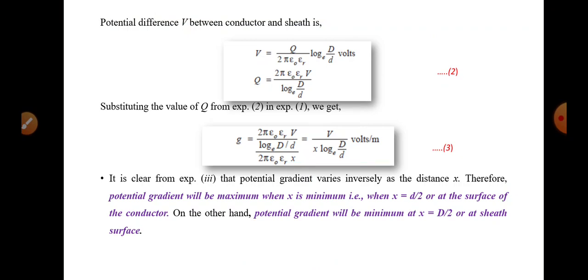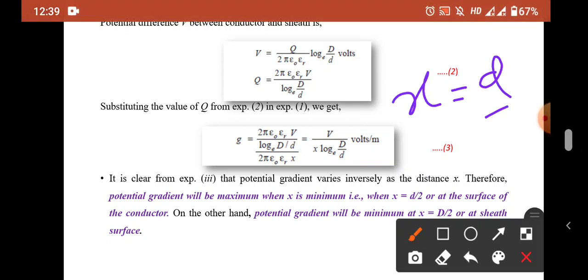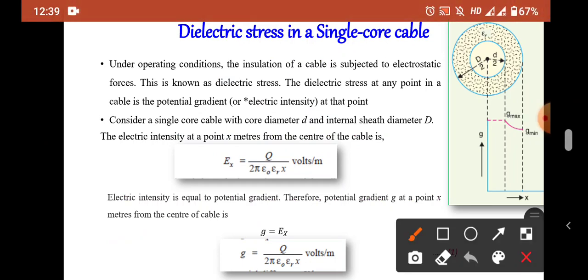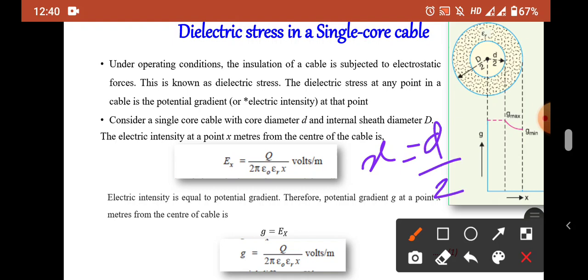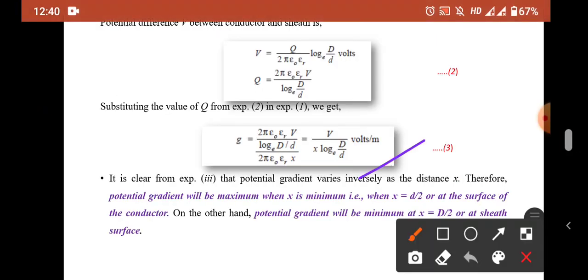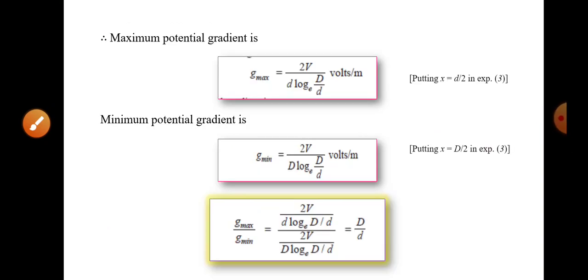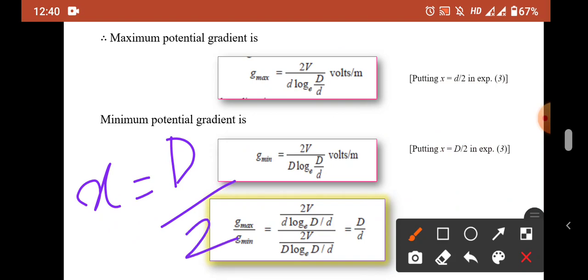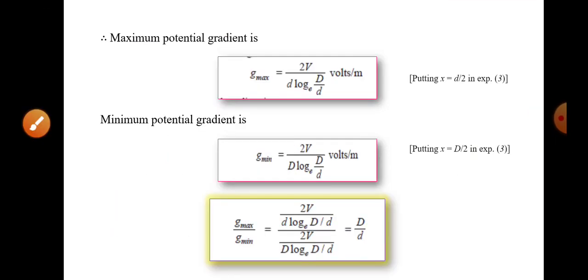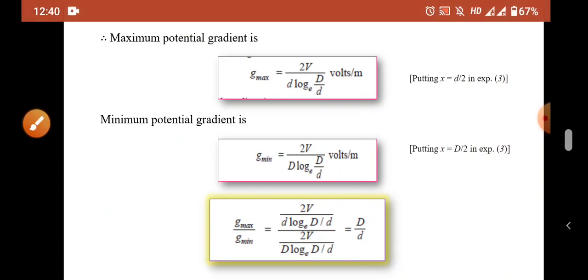To find the maximum dielectric stress, substitute x = d/2 (the radius of the conductor) into the equation for G. This gives: G_max = 2V / (d · log_e(D/d)). For the minimum potential gradient, substitute x = D/2 (the internal sheath radius), giving: G_min = 2V / (D · log_e(D/d)). Dividing G_max by G_min gives the ratio D/d — that is, the internal sheath diameter divided by the conductor diameter. This is the dielectric stress in a single core cable.